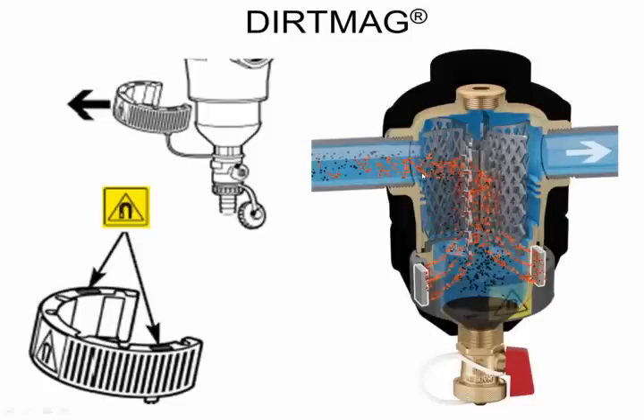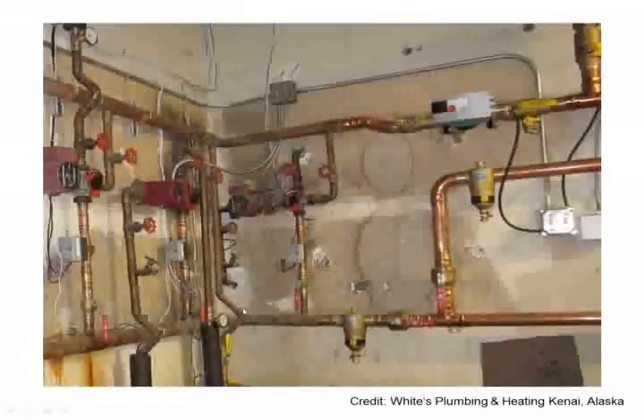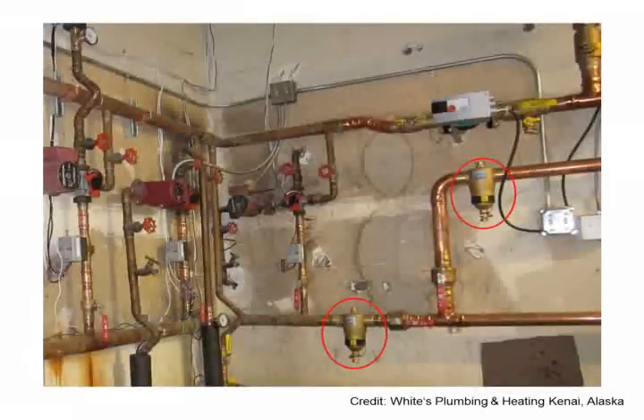So even that very fine talcum powder consistency ferrous oxide, the result of rusting in your system, rather than allow that to get a chance to go and find a home in the system where it's going to create problems, like caking onto a heat exchanger or getting into a pump, we capture it with these magnetic collars. And so we just introduced this feature not too long ago. They're now getting applied in the marketplace. They're very helpful on retrofits.